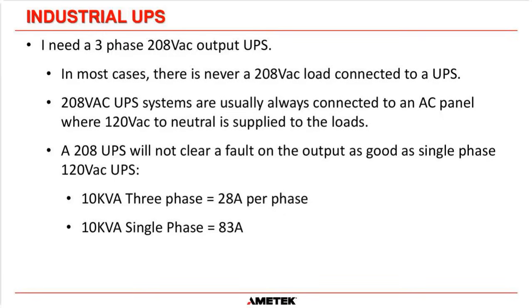And the second line there says they're usually connected to an AC panel where the 120 volts to neutral is applied to a load. And the important thing about this is a 208 UPS will not clear a fault on the output as well as a single phase UPS. Okay. And it's simple engineering math. A 10 kVA 3-phase UPS will only give you 28 amps per phase. Okay. A 10 kVA single phase UPS will give you 83 amps per phase. That's 3.5 times the current.